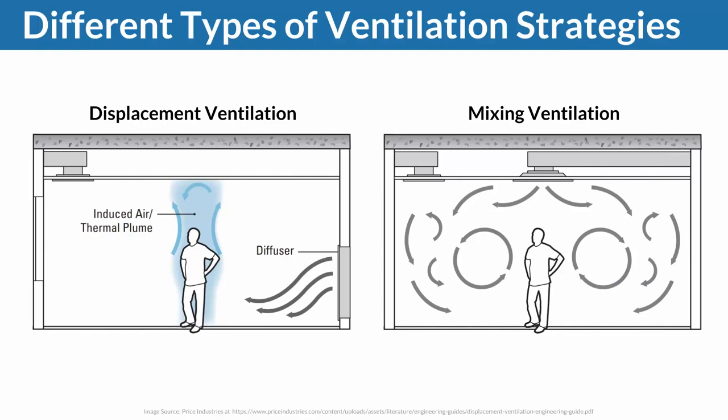Some customers are mainly concerned about noise level — with displacement ventilation you can bring air in at lower speeds, so fans don't have to work as hard and noise is generally lower. Sometimes displacement ventilation doesn't work well in heating applications. There's also a contaminant control component to the discussion. So there's no one right ventilation strategy, and what we want to do today is compare different strategies with CFD for one application.